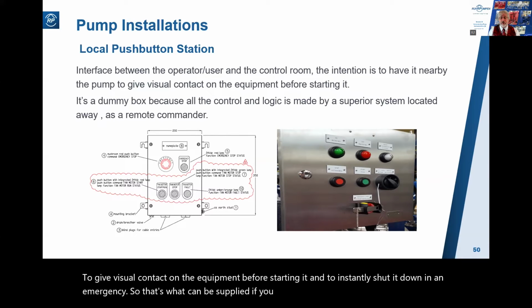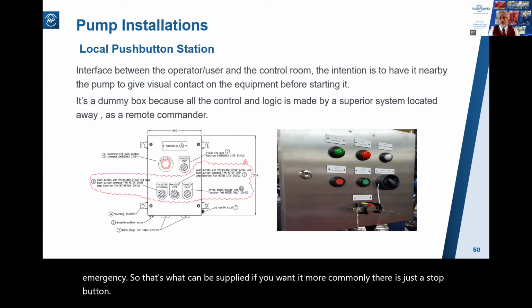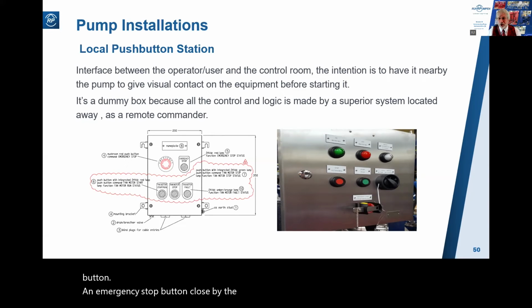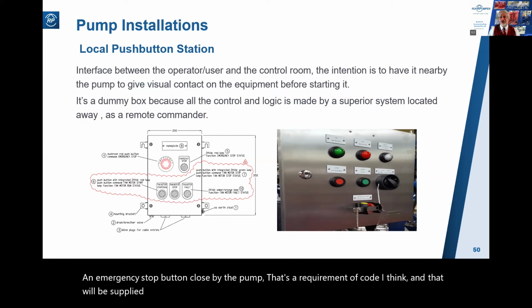More commonly, there is just a stop button, an emergency stop button close by the pump. That's a requirement of code, I think, and that will be supplied normally by the installation contractor, not by the pump suppliers. There's no reason for us to supply a stop button.